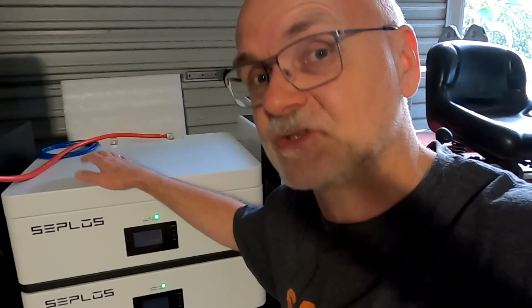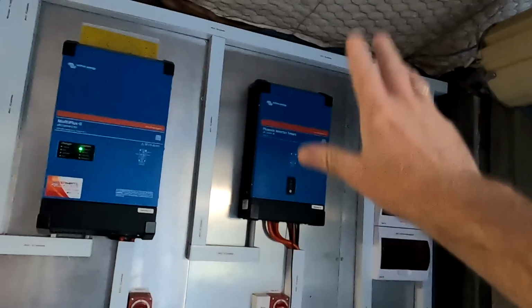And we want to see if the voltage delta has actually come down, because I have charged and discharged these batteries here for the last several weeks. I've mainly used the Phoenix inverter in the afternoon to charge the big battery or heat up the hot water, discharge the battery to around 70%, then fully charge it again to 100% the next day. And every single day we hit the overvoltage protection with all 3 batteries.